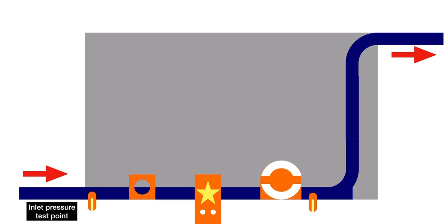But what you do is, you unscrew the little screw in the middle, you don't take it all the way out, you just loosen it. You stick your U gauge on there and it reads the pressure coming into the valve. And you all know you're allowed your one millibar drop. So the first thing it's going to hit is an inlet pressure test point, where you as an engineer test the pressure of the gas going into the valve.